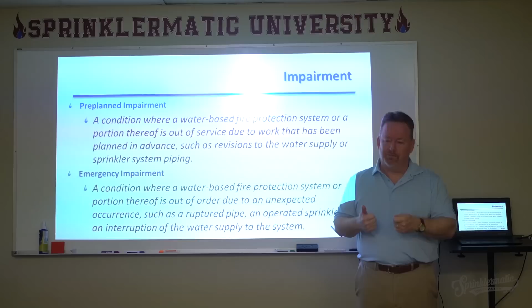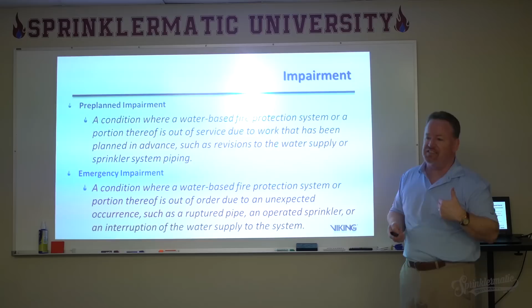The system won't operate, the system is taken out of service. What's important about an impairment is that it has a process to it, detailed at length in Chapter 15 of NFPA 25. So if you say that system is impaired, Chapter 15 immediately becomes applicable. If there's a deficiency, which is something less than an impairment, then you don't go to Chapter 15.